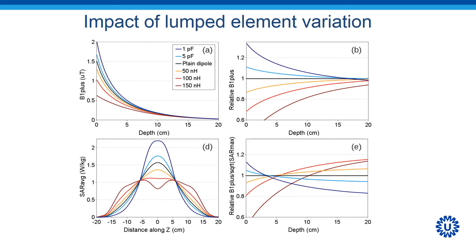It becomes interesting to look at the ratio of B1 plus over the maximum SAR. There we can see that for a depth of 10 centimeters, it's actually inductors, large inductors of 100 nanohenry, that perform the best of all the investigated cases.